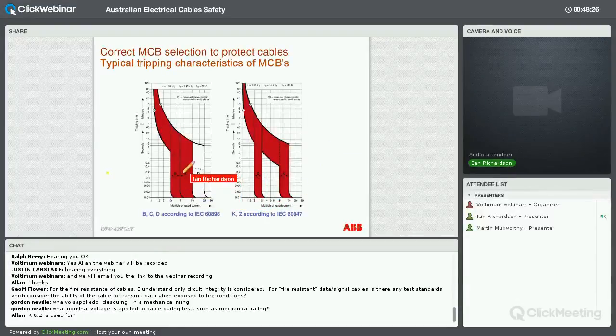Typically, the C curve is the general purpose. The B curve can be used for long cable runs quite often. With a D curve, a lot of people will use them in motor starting or high inrush applications. The Z curve tends to be used more in electronic protection, so something where you want a really fast acting response in the event of a short circuit. And the K curve is actually considered a better option to a D curve because it's not only a little bit tighter from a protection point of view in the thermal part, it's also a little bit narrower in its short circuit value, so it actually offers a higher degree of protection.